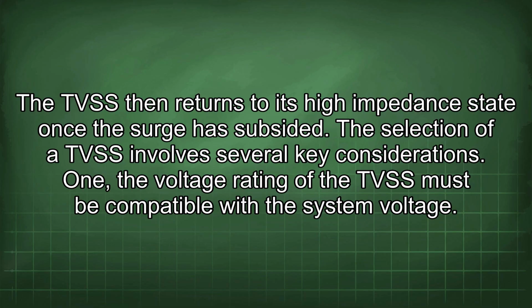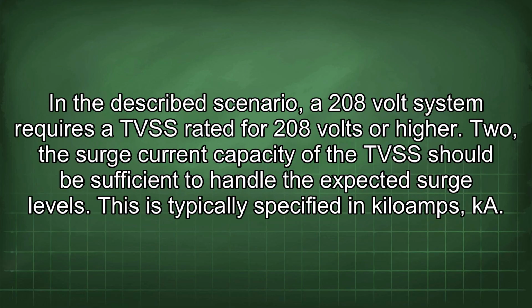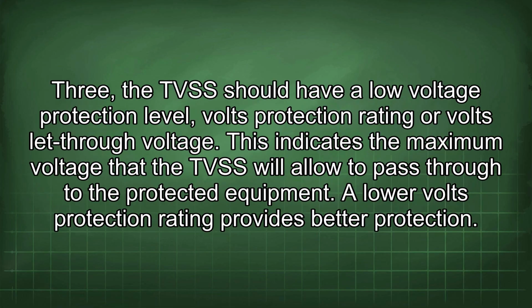The selection of a TVSS involves several key considerations. 1. The voltage rating of the TVSS must be compatible with the system voltage. In the described scenario, a 208-volt system requires a TVSS rated for 208 volts or higher. 2. The surge current capacity of the TVSS should be sufficient to handle the expected surge levels. This is typically specified in kiloamps, kA. 3. The TVSS should have a low voltage protection level, voltage protection rating, or let-through voltage. This indicates the maximum voltage that the TVSS will allow to pass through to the protected equipment. A low voltage protection rating provides better protection.